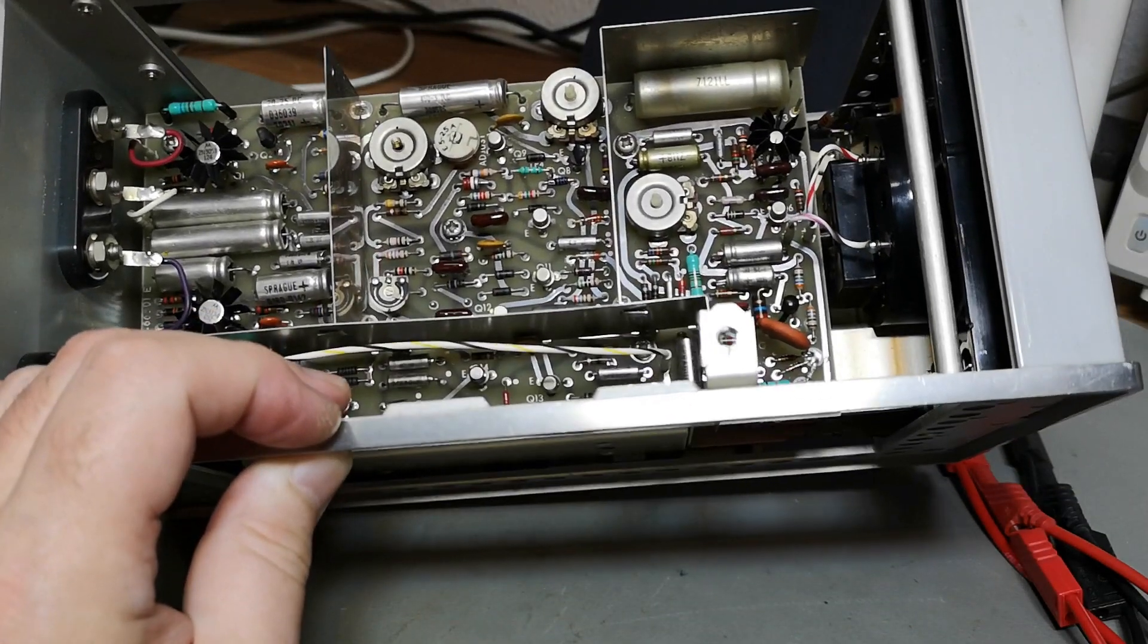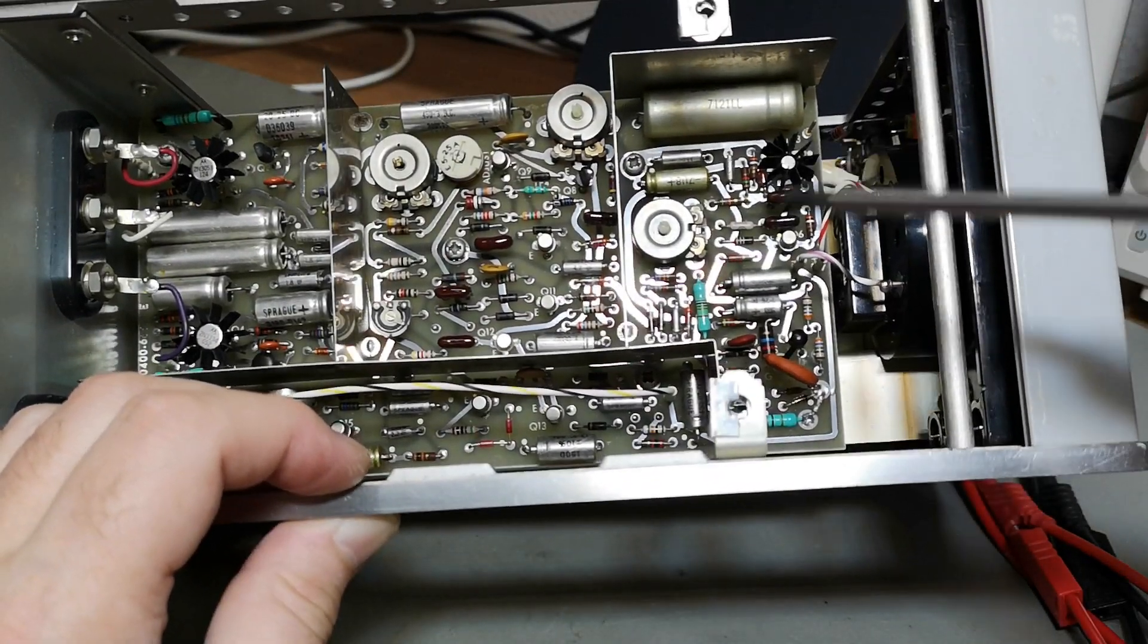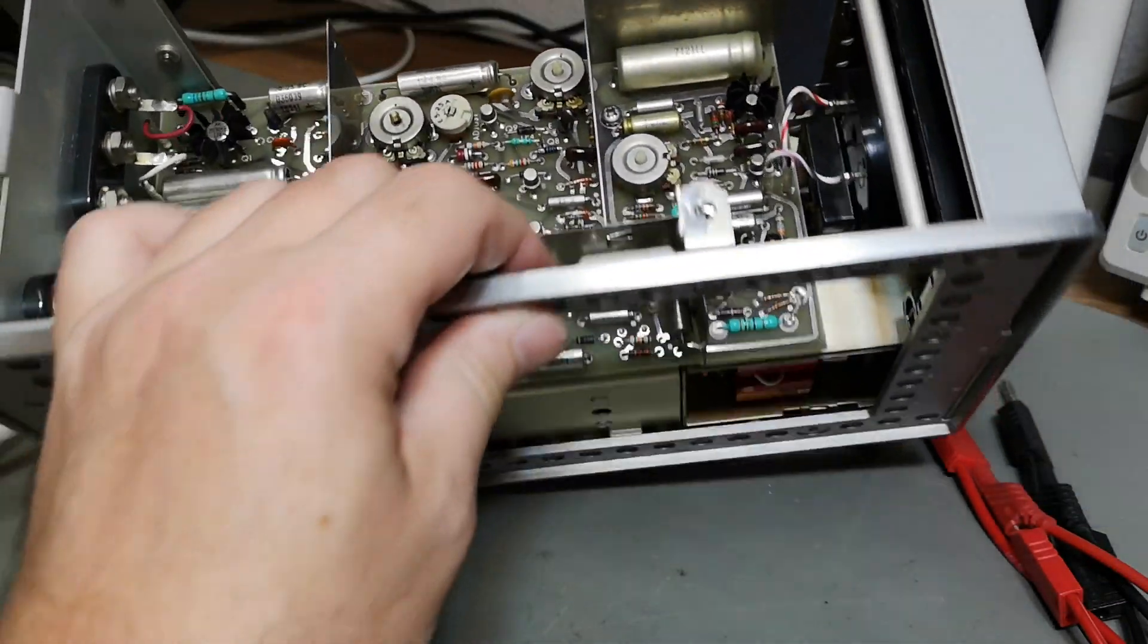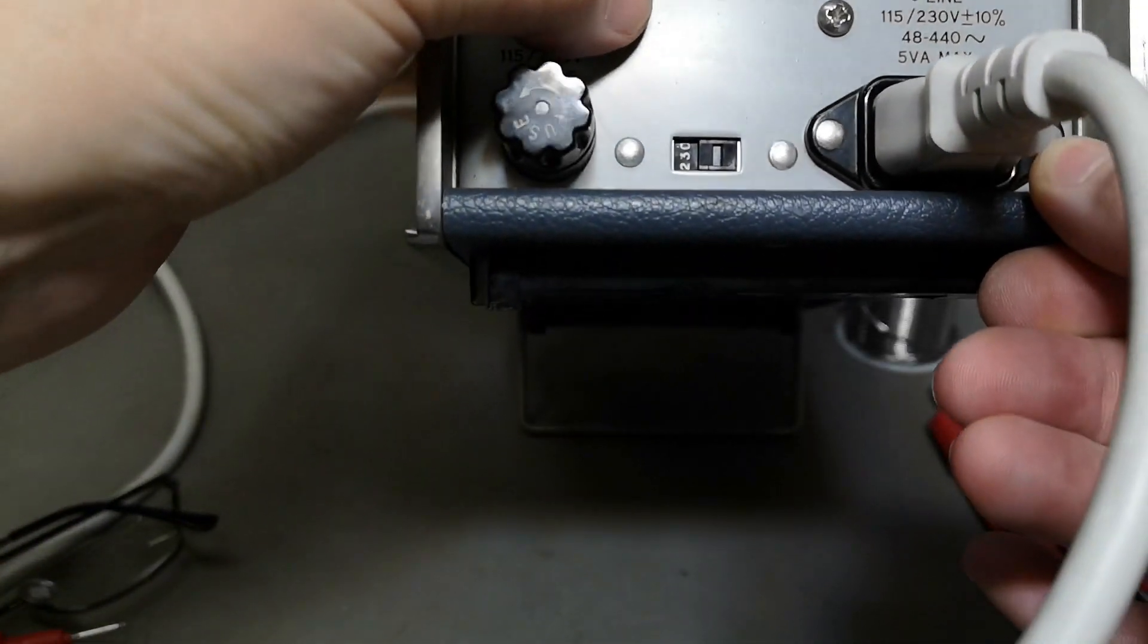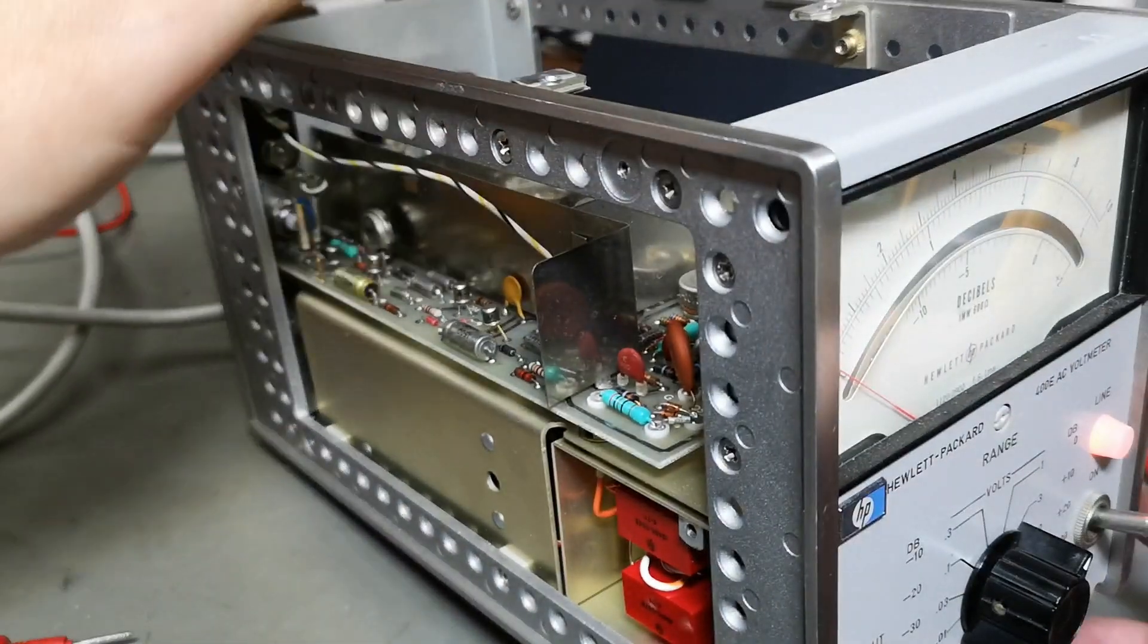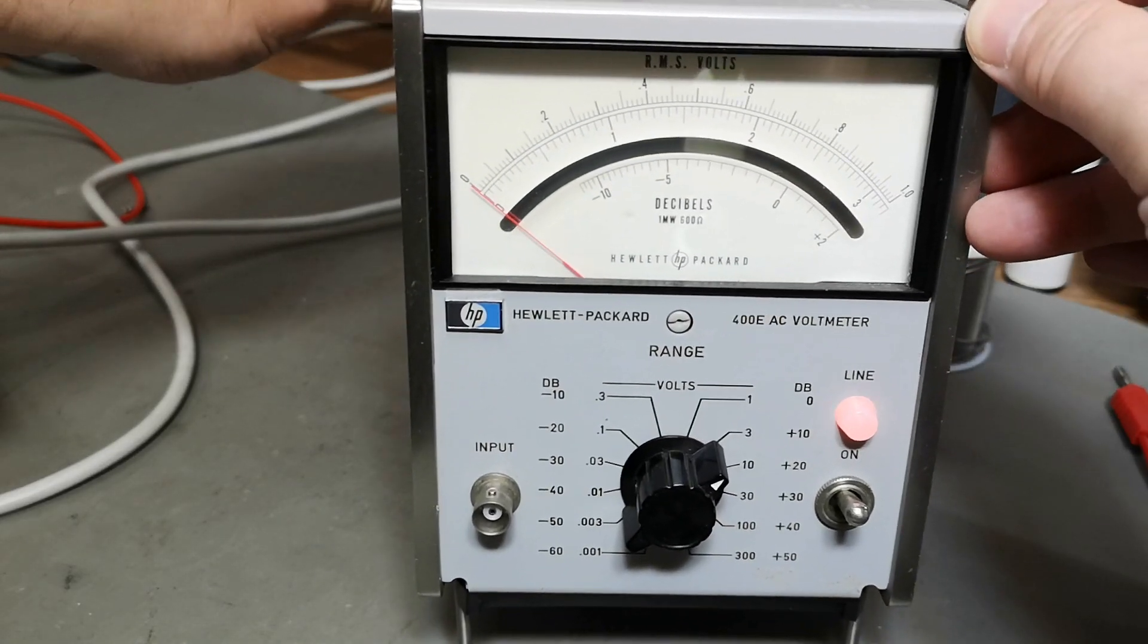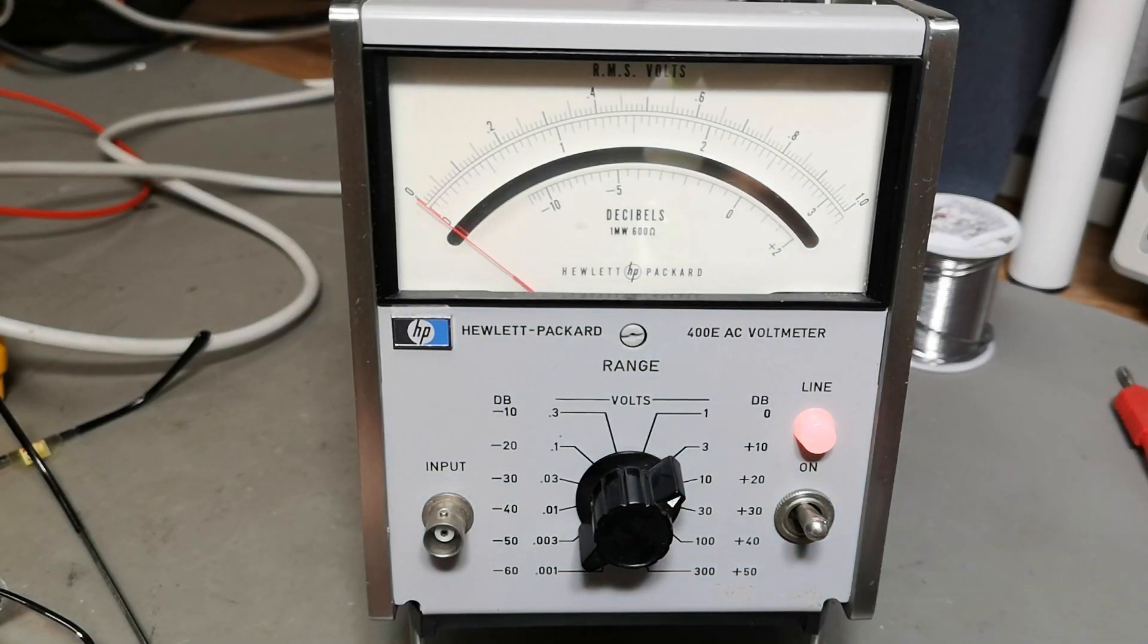There is no other way, by the way, to adjust this instrument. So I followed all the guidelines in the manual. I measured all the different points on all the different trimmers and adjusted all the voltage points so they're correct. And I went up and down in the frequency range and played with the trimmers that have something to do with frequency compensation and all that kind of stuff. So now I believe this instrument is just as good as it would have been in 1969. I think there is a, yes, there is. The serial label ends with, or starts with, 09, so that means this instrument is from 1969, and now it is back to super-duper full function. Yeah, that was all I wanted to show you guys about this, yeah, a little bit more simple, probably also a little bit more cheap compared to the other one I showed in the previous video. Cleanup time here. Thank you for watching, bye-bye.